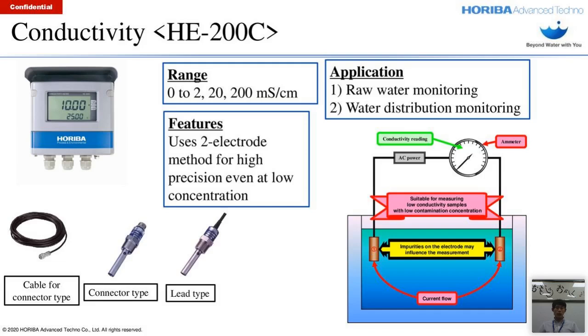The good thing about this is that when a sensor is broken, only the sensor needs to be replaced. So this makes the replacement cost easier and cheaper. While on the other hand, for the lead type, the cable is attached to the sensor by default. When the sensor is broken, the entire sensor along with the cable needs to be replaced. However, the lead type sensor has more configuration options and it can be immersed into a tank while the connector type cannot. So that is the main difference between the lead type and the connector type.